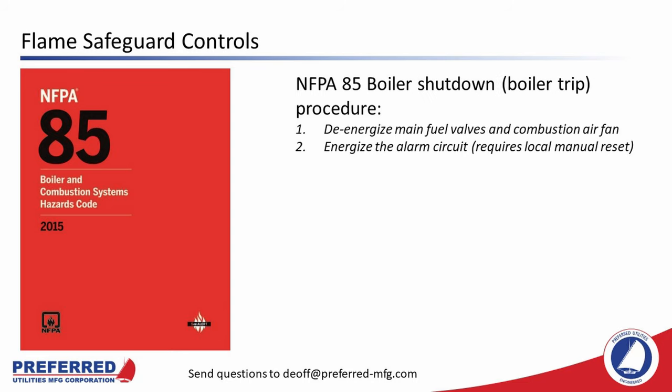On a boiler trip, there is a different procedure. A boiler trip occurs in more serious situations — like a flame-out or a gas pressure switch being tripped. The flame safeguard controller will de-energize the main fuel valves and the combustion air fan and energize the alarm circuit. This requires a local manual reset: an operator must go out to the boiler and make sure it is safe to light off again before hitting the reset button. Otherwise the burner stays shut down in alarm.